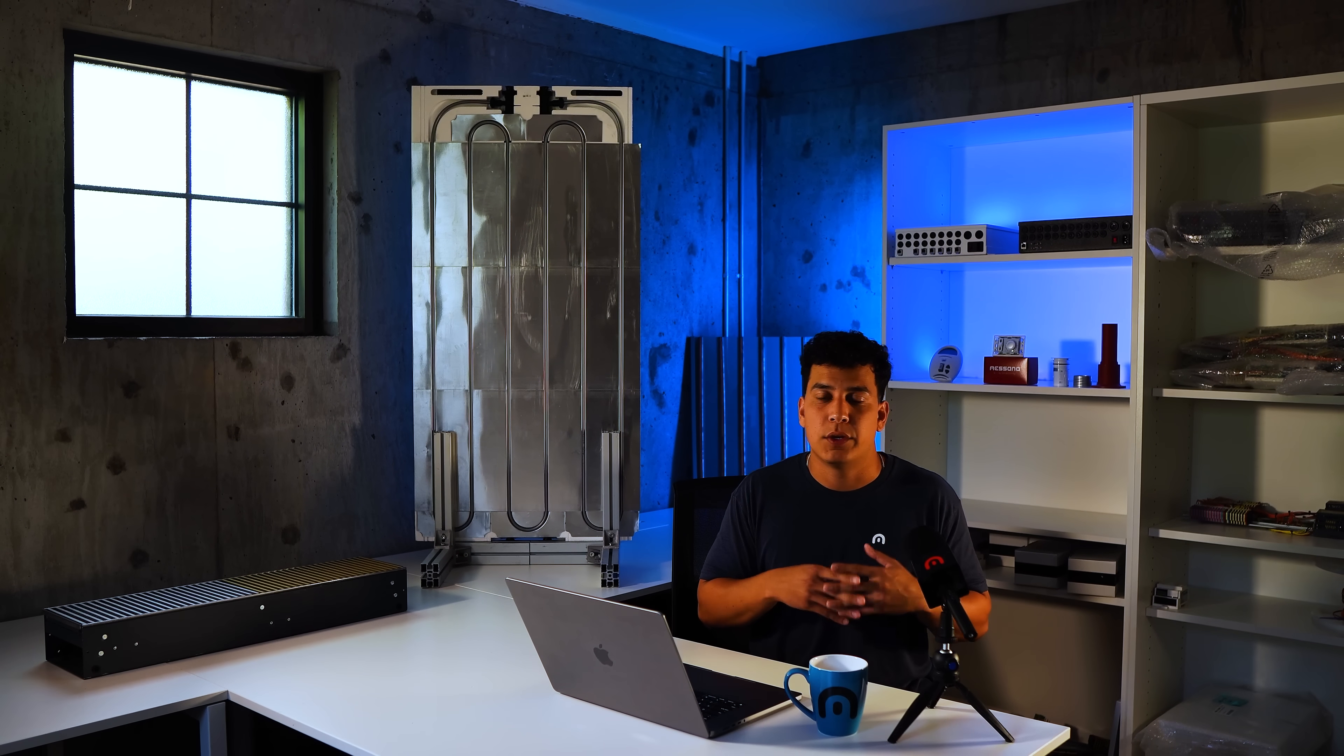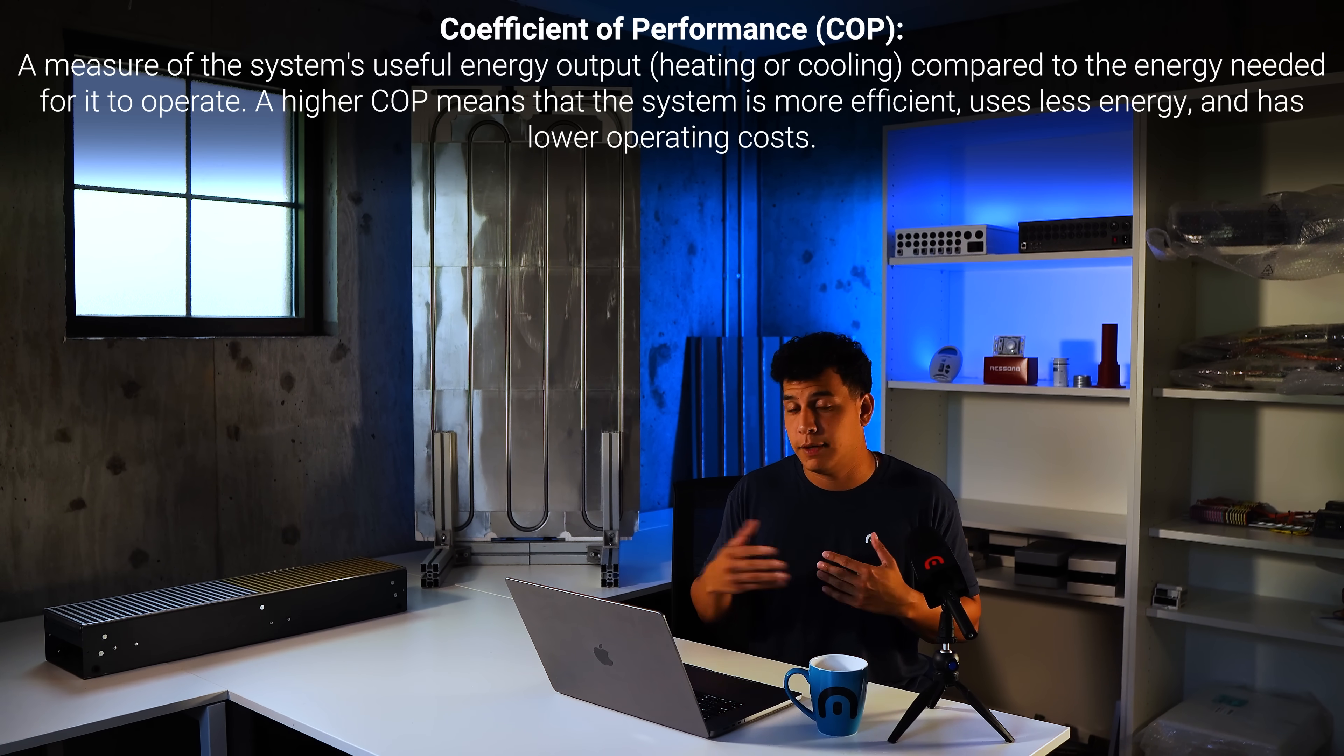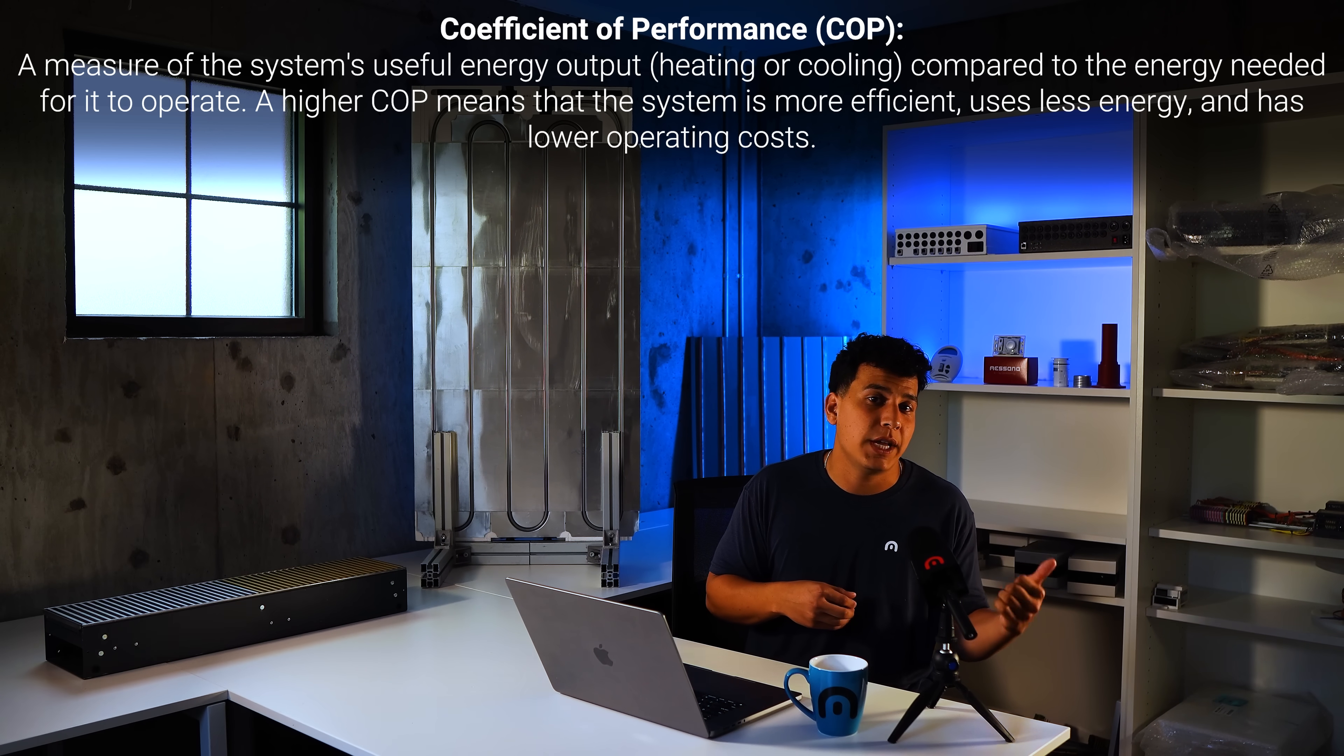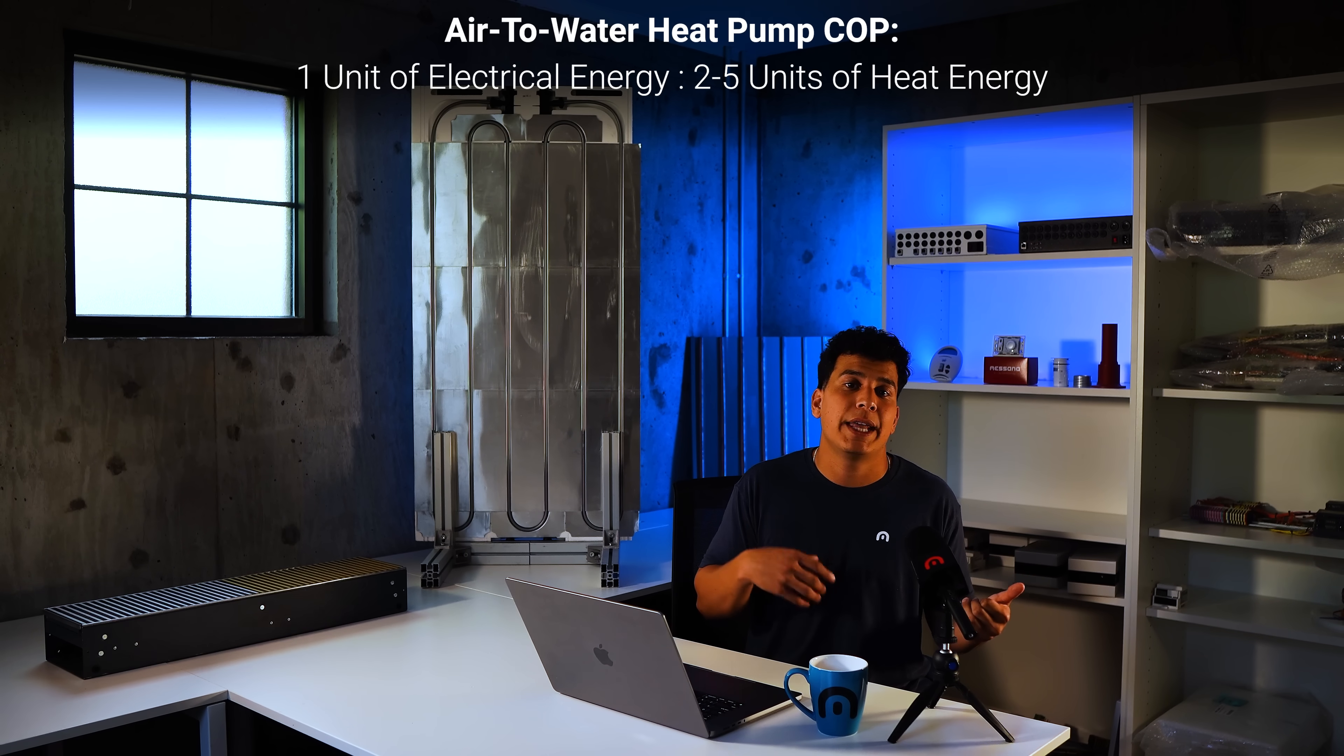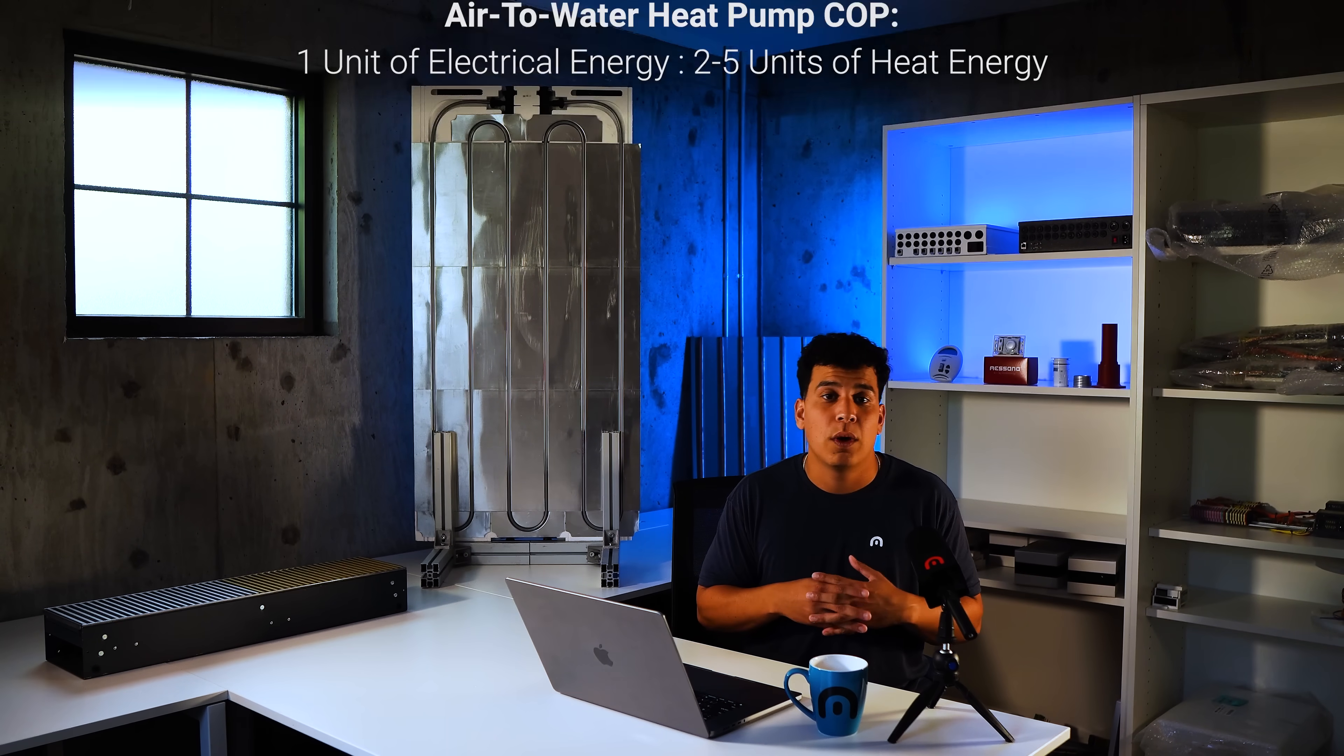So on the sustainable side, devices like air to water heat pumps are highly sustainable, highly efficient. There's a term that's coefficient of performance and that reflects the efficiency. And so basically for every one unit of electrical energy input, how many units of heat energy do you get out? And so for every one unit with an air to water heat pump, you're getting anywhere from two to five units of heat energy out. So you're getting a positive return on your investment.